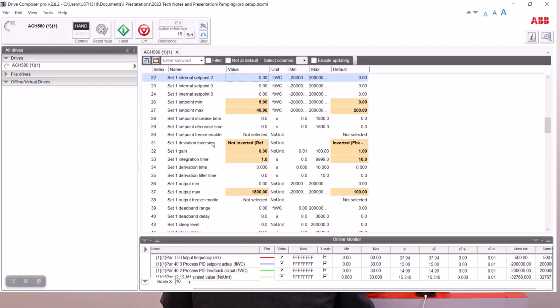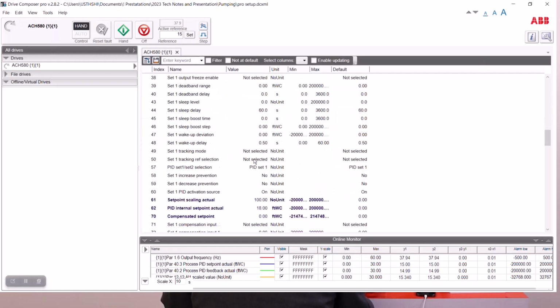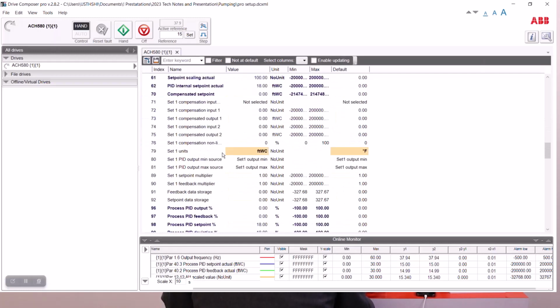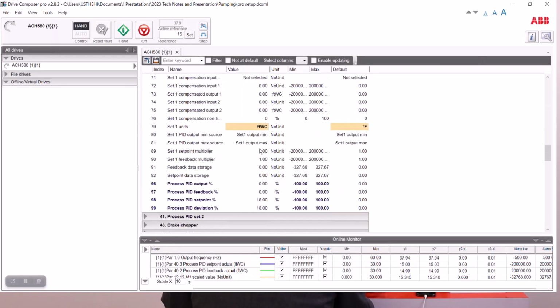My deviation inversion is not inverted. My gain is 0.3, and my integration time is 1. These were all set up to allow the system to be stable for this system that I'm using. And my units are feet of water column right here.